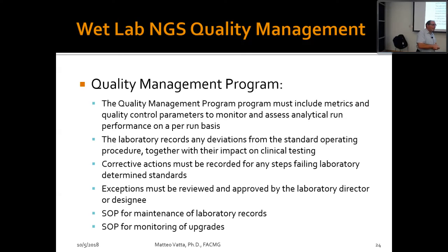Between updates of software, if the developer decides to change the format of the output, is that a criterion to not update? Everything has to be analyzed, validated, and then approved by the lab director. Whatever was written before, which is essentially the step-by-step of how to do the test, whenever there is an implementation, an update, or any change, needs to be compared with the previous system, to prove that it is doing exactly the same job or even a better job.